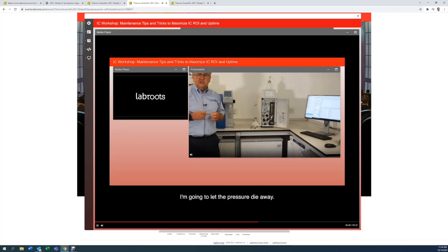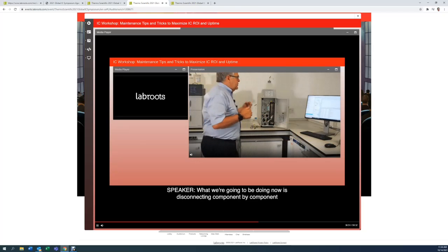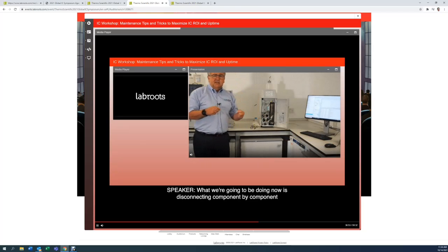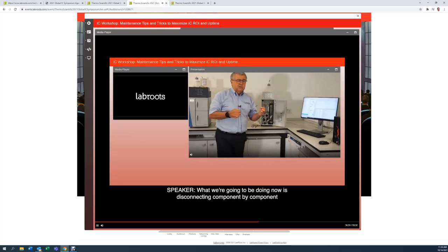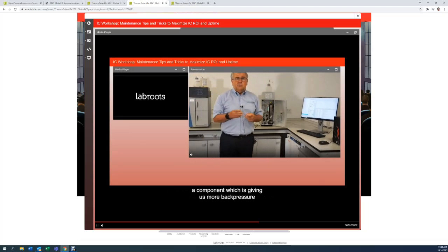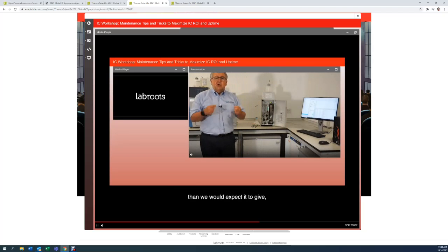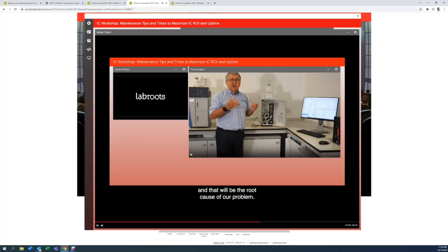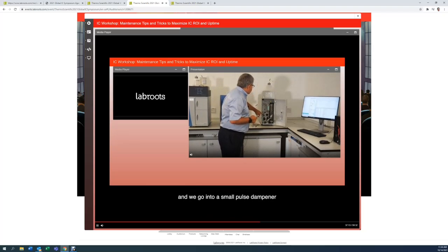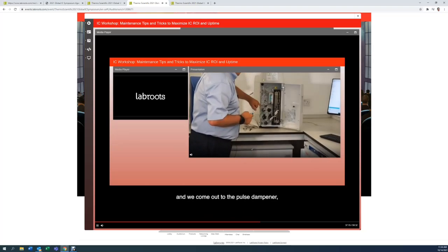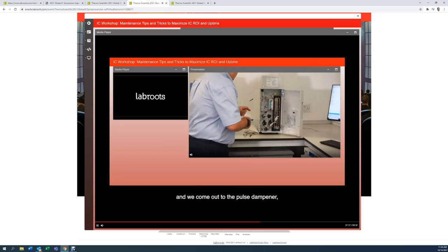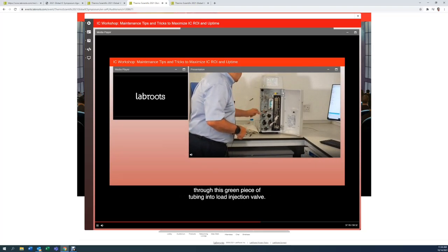I'm going to let the pressure die away. What we're going to be doing now is disconnecting component by component along the flow path of the instrument until we come to a component which is giving us more back pressure than we would expect it to give, and that will be the root cause of our problem. So from the pressure transducer, we go in on the ACU, we go into a small pulse dampener, and we come out of the pulse dampener through this green piece of tubing into a load injection valve.